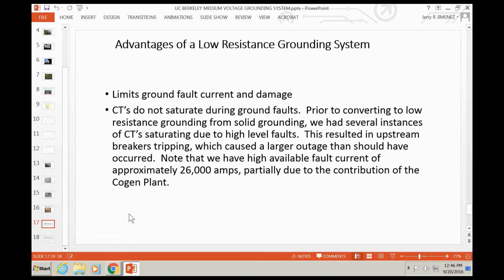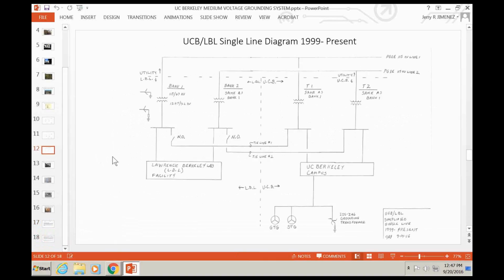Well, one other question, and I'm going to open it up here, that I have is, the utility didn't have a problem with the resistor when you upgraded. They are your transformers, right? But even if they are your transformers, we often will get pushback from the utilities that say we have concerns about ferroresonance and other phenomena you get with grounding on the customer secondary side, and they prohibit it. It strikes me that you might have had a special case because of the mission of the Berkeley laboratory. But in our morning session, we did talk a bit about that. It seems to be something that many engineers run into when they're dealing with a high voltage service with the utilities for a campus power system.